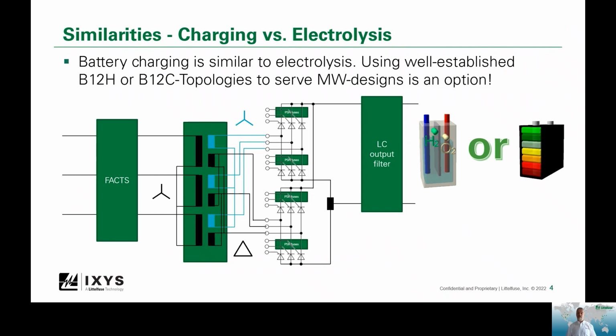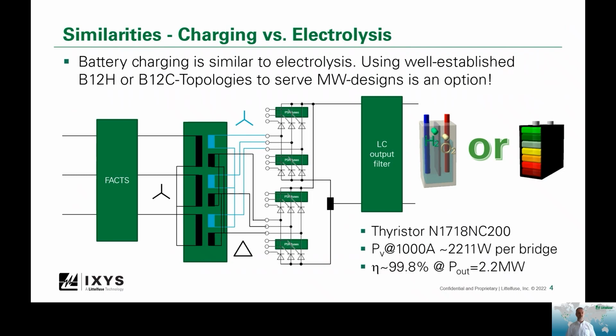If based on thyristors, efficiency becomes a really good factor. Even with a classic thyristor in place, the losses in this thyristor at 1000 amps of throughput, the whole bridge only creates 2 kilowatts of losses, but achieves a megawatt of throughput. This leads to an efficiency in the regime of 99.8% at a throughput of 2.2 megawatts. Sounds too good to be true? It's not. So, taking a look at the thyristor and the efficiency issue.